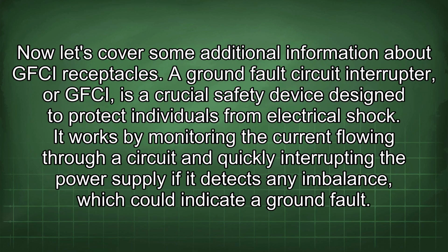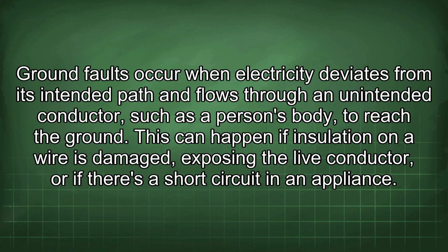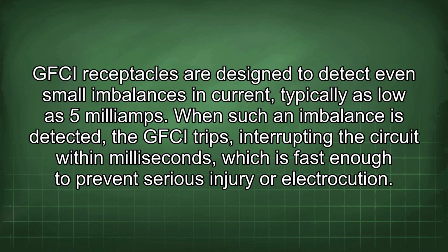Now let's cover some additional information about GFCI receptacles. A ground fault circuit interrupter, or GFCI, is a crucial safety device designed to protect individuals from electrical shock. It works by monitoring the current flowing through a circuit and quickly interrupting the power supply if it detects any imbalance, which could indicate a ground fault. Ground faults occur when electricity deviates from its intended path and flows through an unintended conductor, such as a person's body, to reach the ground. This can happen if insulation on a wire is damaged, exposing the live conductor, or if there's a short circuit in an appliance. GFCI receptacles are designed to detect even small imbalances in current, typically as low as 5 mA.